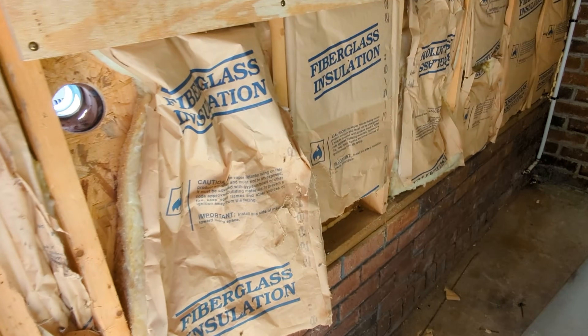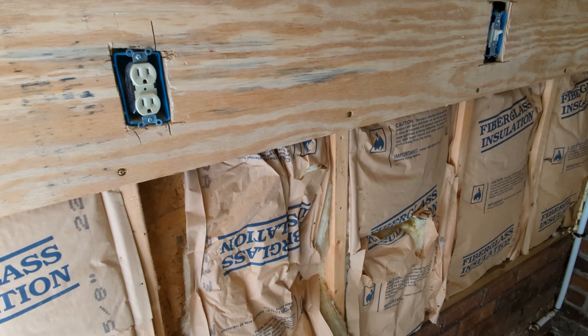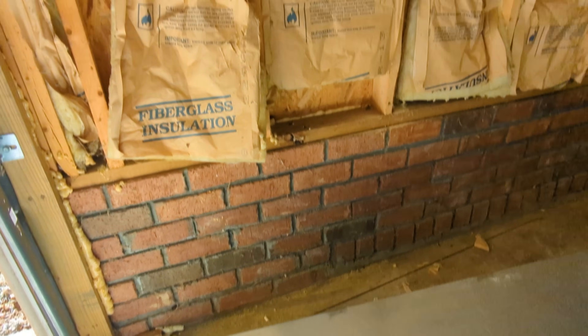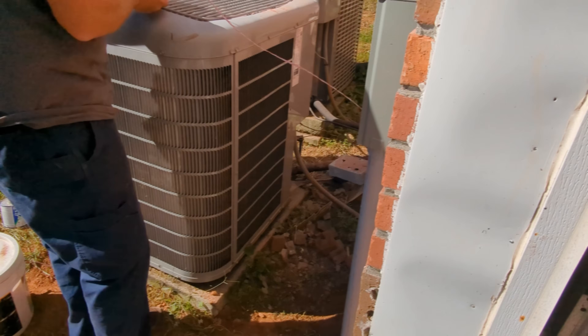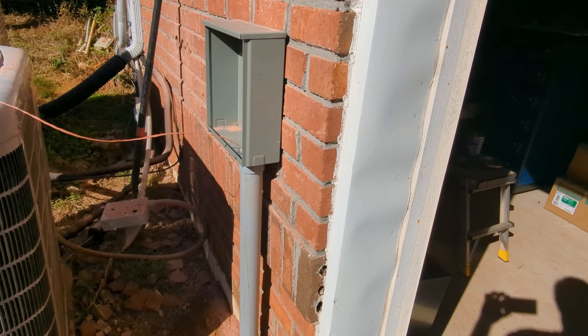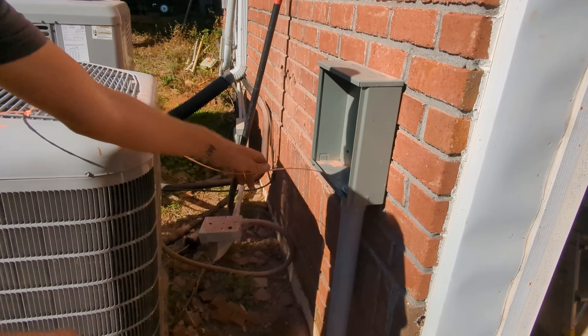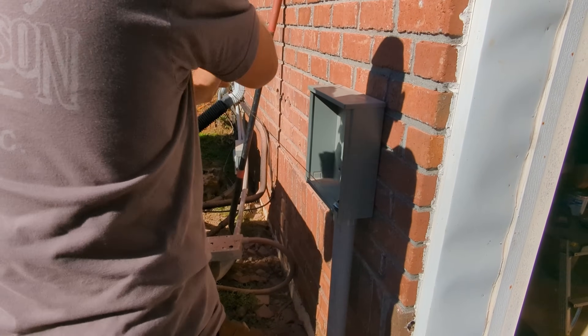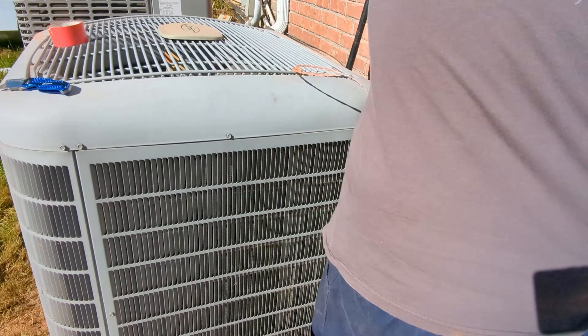The gutter came back down, so one of the not-so-fun tasks is getting all the holes right and not forgetting any — one for the solar, all the back-and-forth for the AC, the power distribution blocks — all that stuff has to be punched in this gutter. You kind of do a layout, do all your pilot holes, and then bore through the brick. Thankfully it's only a veneer of brick today — sometimes we've got to go through full brick and block, and that's not fun. Now he's going to pull the pull string back so you can pull the mule tape in.